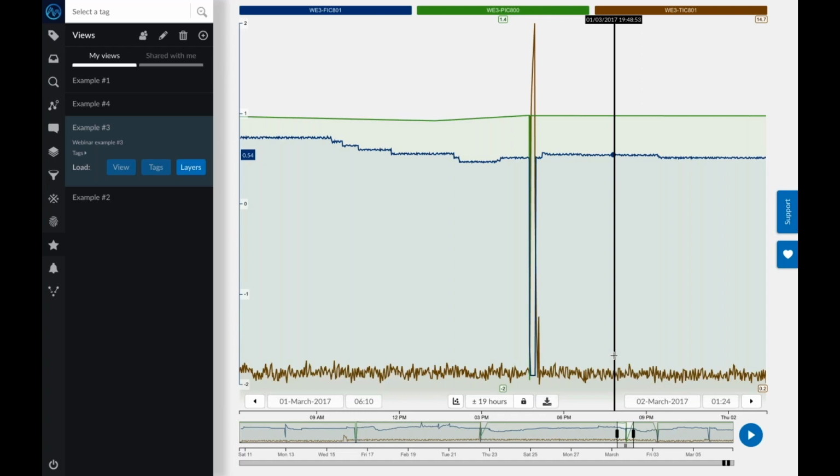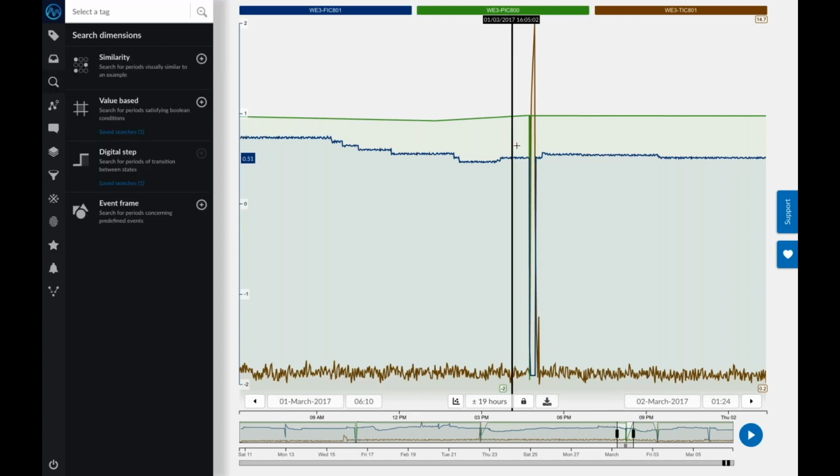So once we saw that, we tried to investigate, okay, can we prevent those peaks? But unfortunately, that was not possible because it was related to the compressor, and it was not possible to do maintenance on the compressor while the line was in production, of course. So what did we do? We went one step further, and we started thinking, okay, we cannot avoid the situation from happening, but at least I would like an early warning. I would like to find out when that happens. Can I trigger some early warning so that the operators still have ample time to take appropriate action before it is too late, basically?